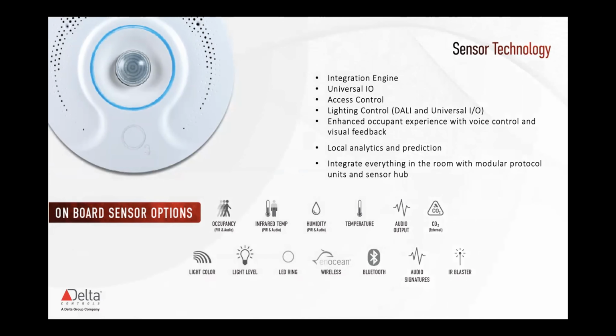Our president's office is all set up so he can select a standard day mode, where the blinds are open and lights are at full intensity for working. Or he can hit a button for meeting mode, which drops the blinds, dims the lights, and uses the IR blaster to turn on the monitor for a meeting. Now, the last thing is it does have CO2 — however, it's not actually on board.